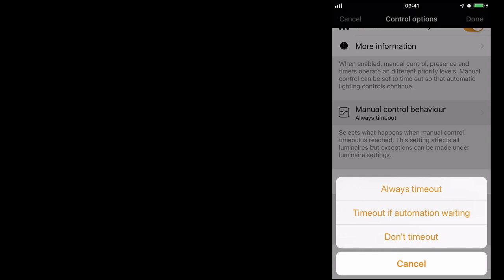Always time out means any manual control will eventually time out. Time out if automation waiting means if the particular luminaire or group of luminaires are being controlled by either a timer or a sensor, they will time out only if they're being controlled. A luminaire which is not being controlled by a timer or a sensor will not time out.